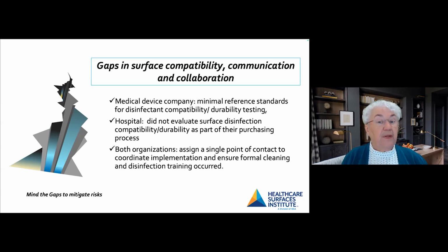They did them, but they weren't looked at for the whole length of time. The hospital did not evaluate surface disinfection compatibility and durability as part of their purchasing process, which they could have done had they had a big coordinated effort with collaboration and communication.